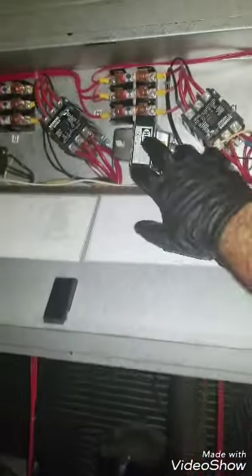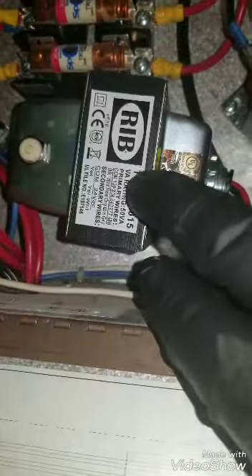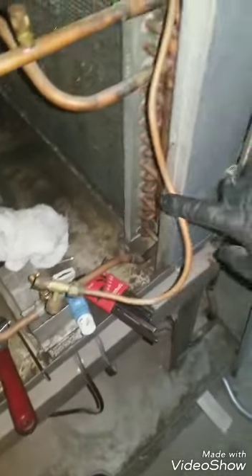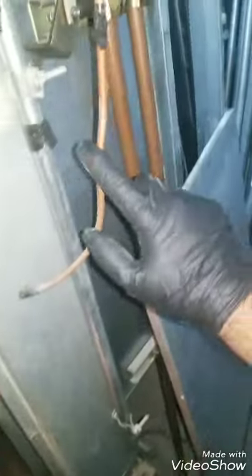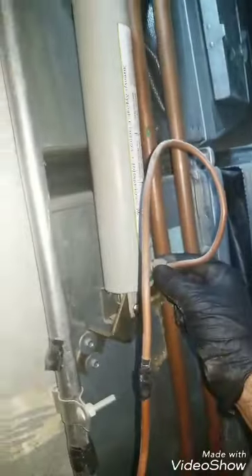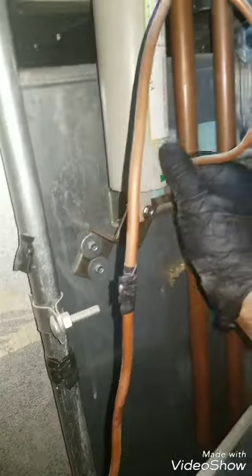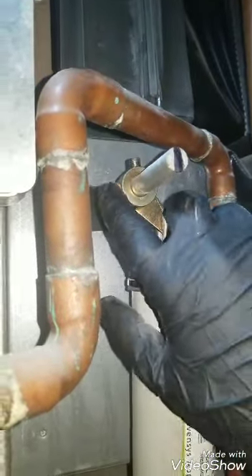Alright, first step, you recover the gas. Take the gas out of the system. Second step, mount your transformer, 50 VA. Then you come over here. You remove your Robertshaw piston. Comes over here. All right. Take that off. Loosen up these set screws right here.